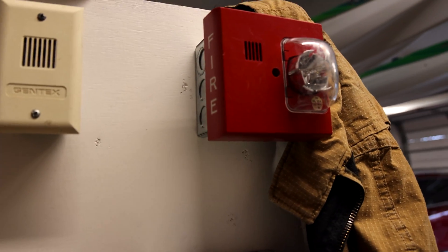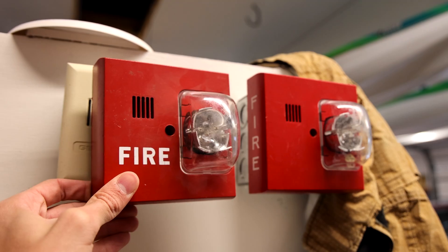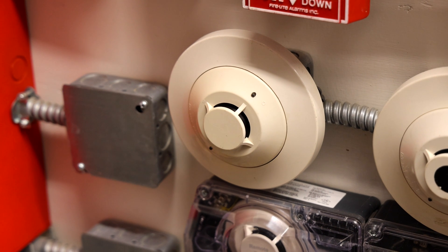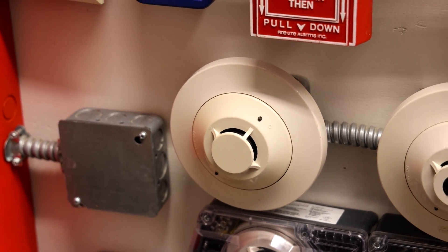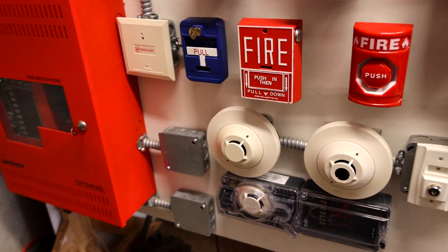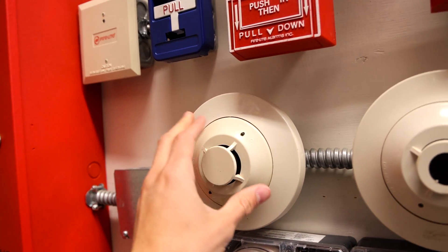And then if we look at this alarm, I have a Siemens UMMT horn strobe — yeah, they're pretty much the same thing. To finish out the system test, we're going to activate this Fire-Lite SD355 Photoelectric Addressable Smoke Detector. But before we do that, I'm going to show you something. I'm going to go ahead and take the head off of the smoke detector.